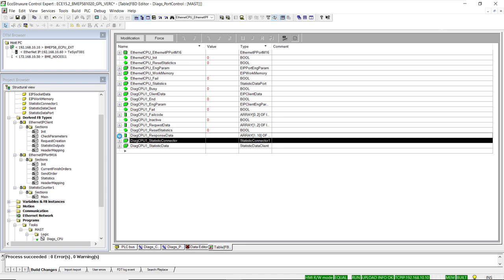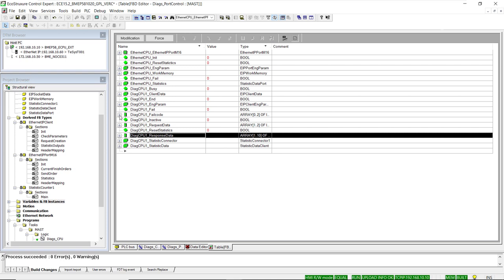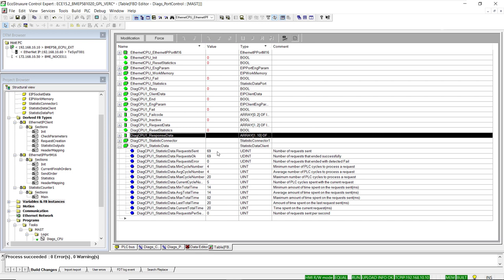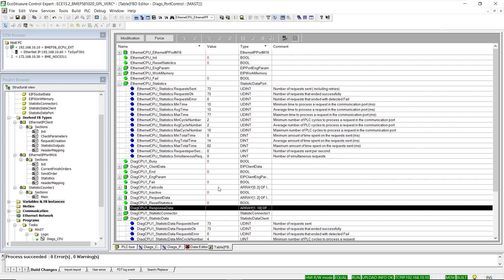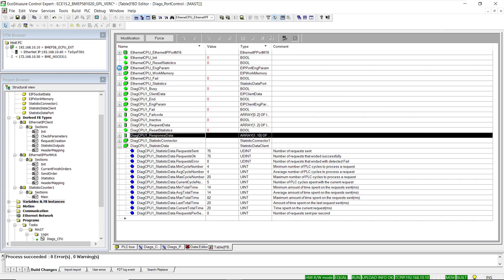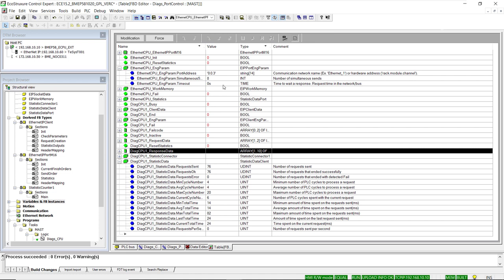Going back to the animation table, we can inspect diagnostic information. In the fail code structure, all values are 0, indicating correct communication. The statistic data array shows a count of OK messages and messages in error — in this case no messages were sent in error — as well as minimum, average, and maximum communication transaction times. A similar structure exists for the port function block itself, and we can confirm the engineering parameters were transferred correctly.